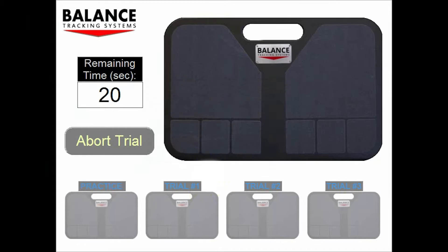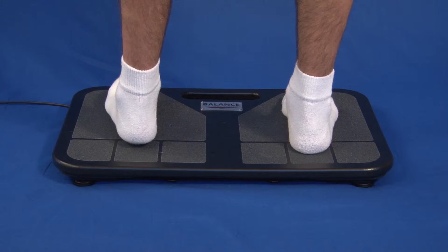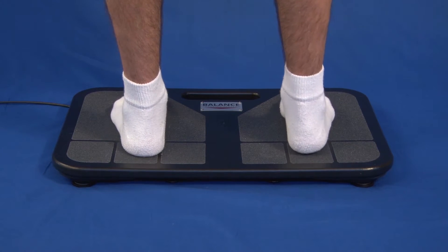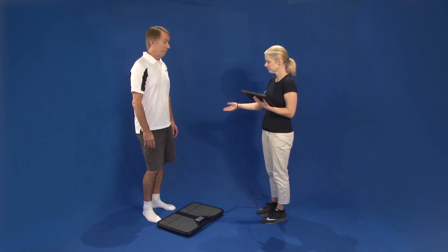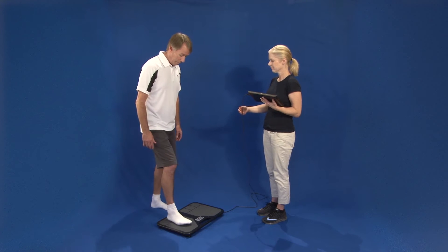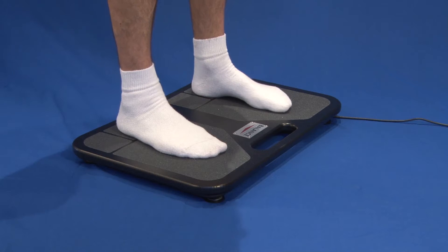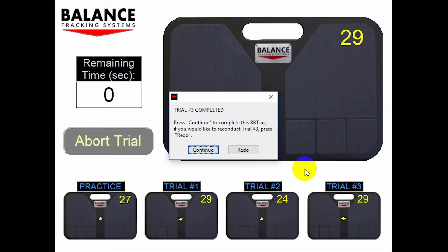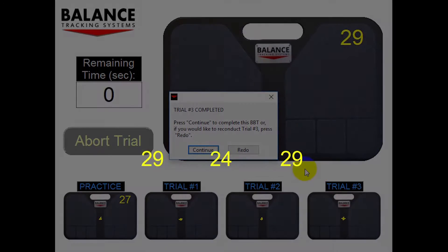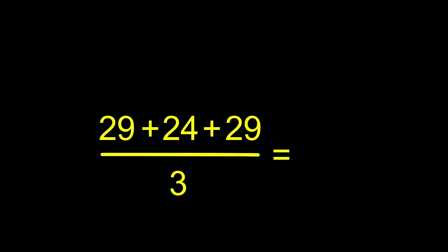Then we proceed with the testing. There are four trials, each lasting 20 seconds. Each trial measures the centimeters of postural sway. The first trial is a practice trial to familiarize the individual with the testing procedure. The next three trials are actual balance tests, and their results are averaged together to get the B-Tracks Balance Test result, called the BBT.